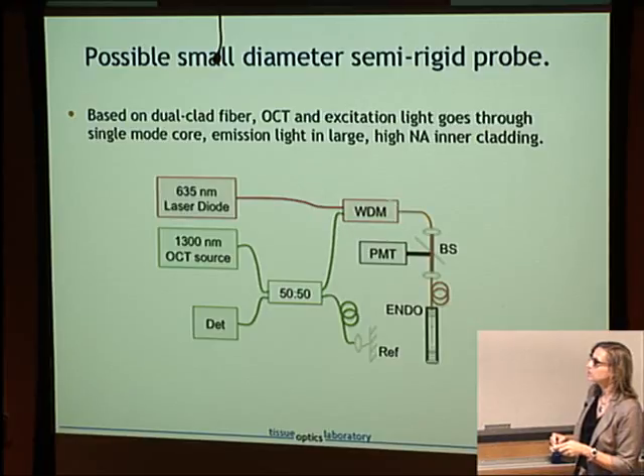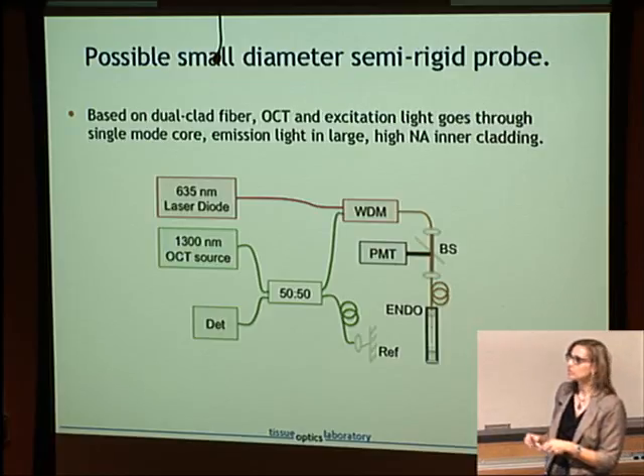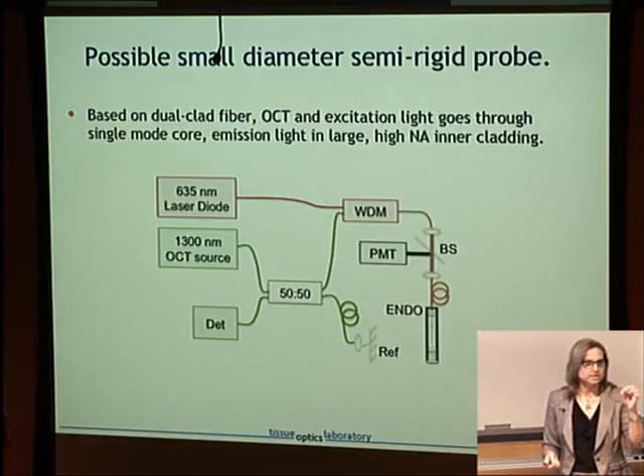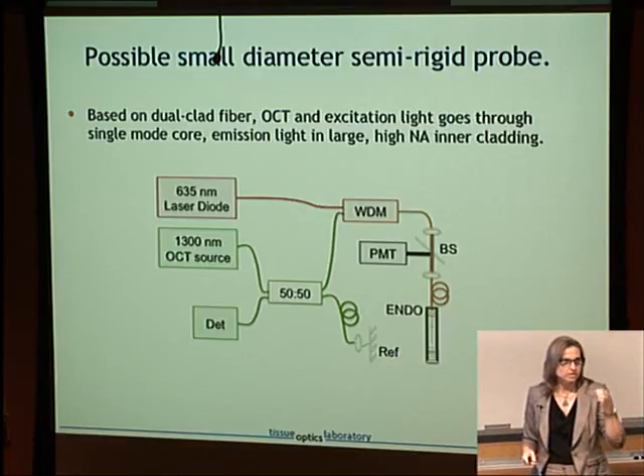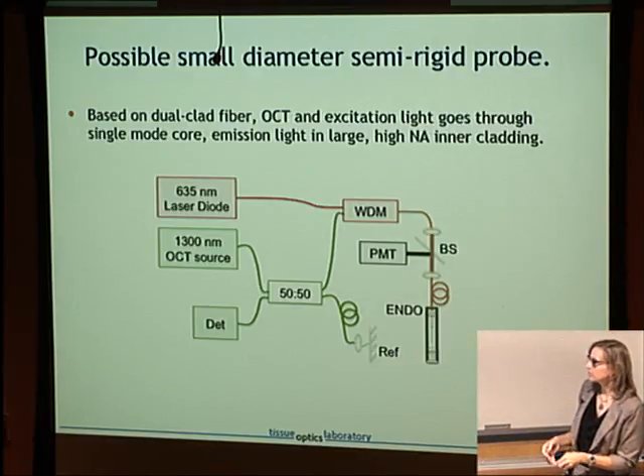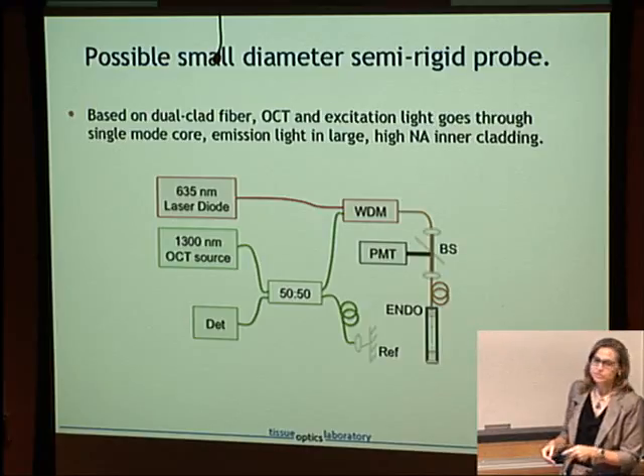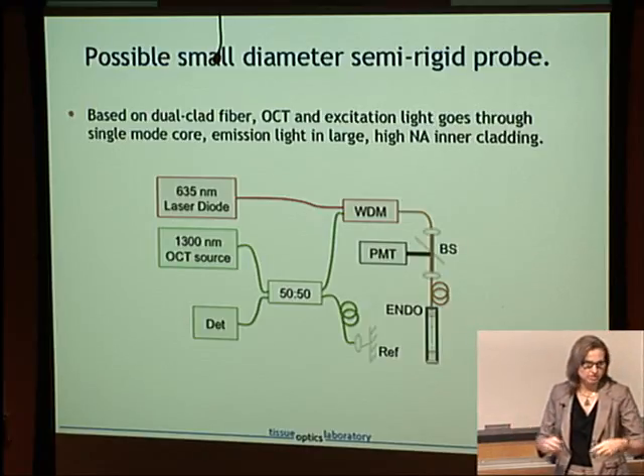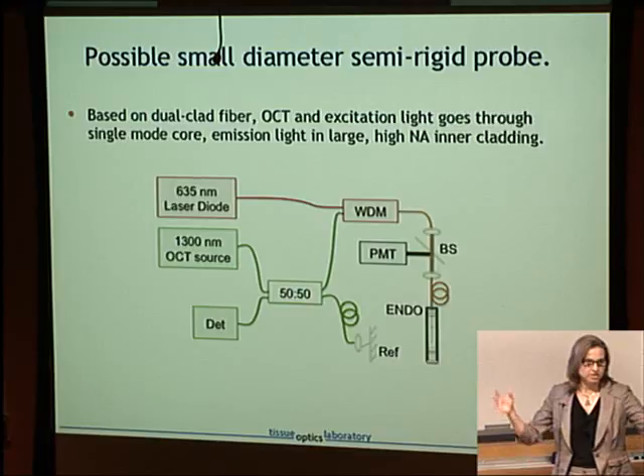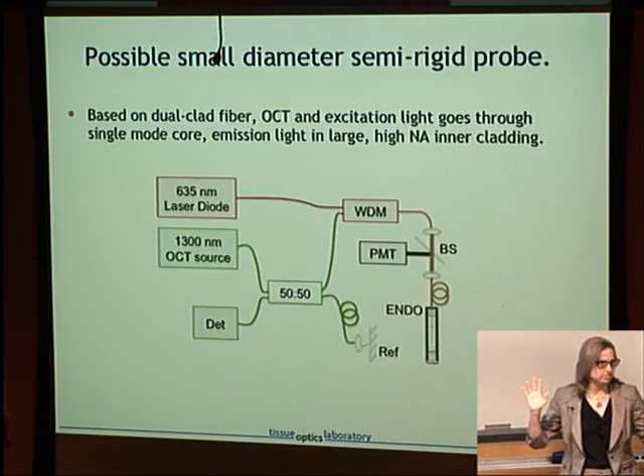So we could combine these two wavelengths in the wavelength division multiplexer and put it into a dual core, dual clad fiber. And so we combine them and we run both the excitation light and the OCT into a single mode core of a dual clad fiber. And then what will happen is this light will shine on the tissue, the tissue will fluoresce, the OCT light will come back, the fluorescence light will come back, and that will be traveling both through the core and the inner cladding.